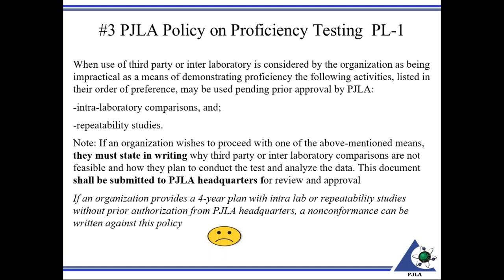So recall that it's stated in 17025, where available and appropriate. There are instances where it is not. One common example is a truck scale. Kind of hard to conduct an interlab test, and there are no third-party providers. There is some proficiency testing where you may get approved to do intralab testing. If there is a known third-party provider, chances are it is not going to get approved. But if you feel you fall in that scheme where it is not available and it is appropriate to do an intralab test.